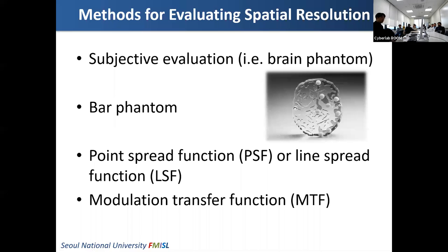The more professional physical way is to measure the point spread function or the line spread function using a point source or a line source. Another very mathematical way is to measure the modulation transfer function, MTF. MTF is usually measured in x-ray systems; in nuclear medicine, we more frequently use the point spread function.